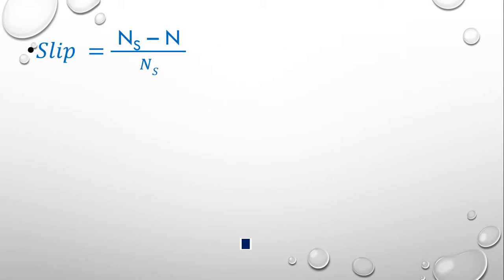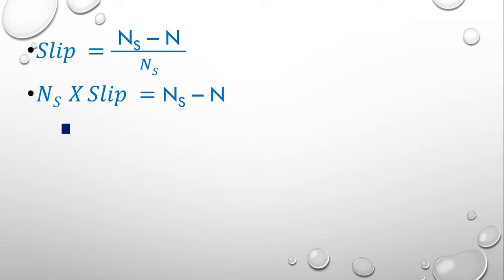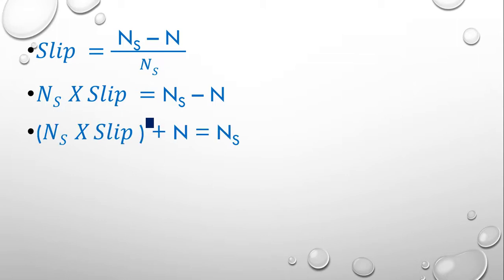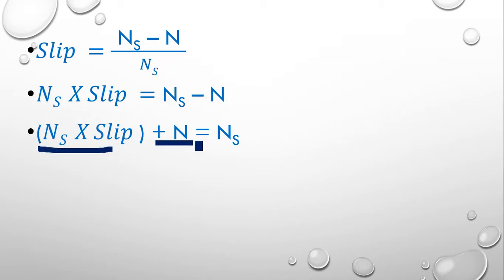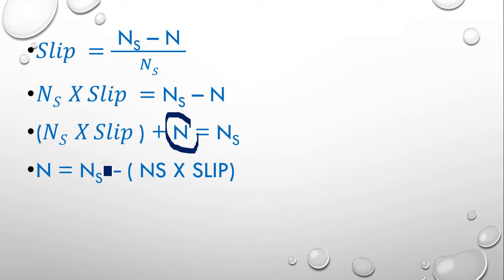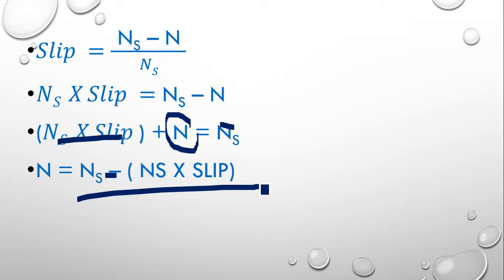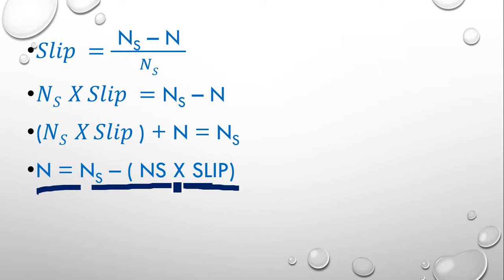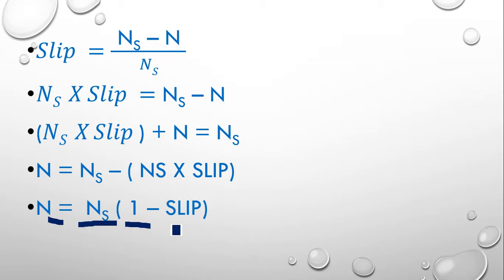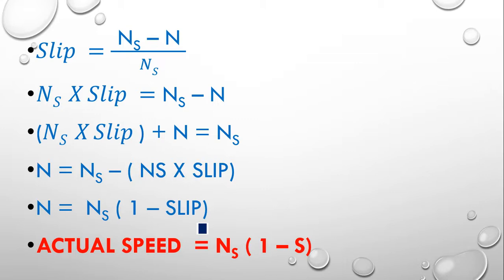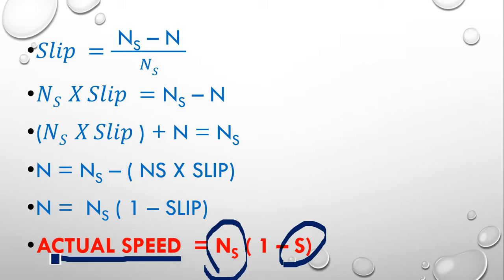We can derive an equation for actual speed from the slip equation. Starting from S = (N_s − N) / N_s, multiply both sides by N_s: N_s · S = N_s − N. Rearranging: N = N_s − N_s · S = N_s(1 − S). So actual rotor speed = N_s × (1 − S).